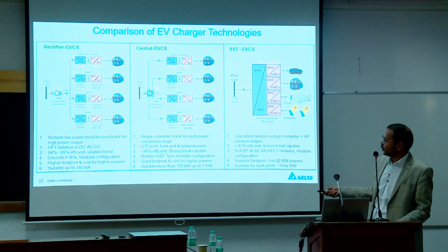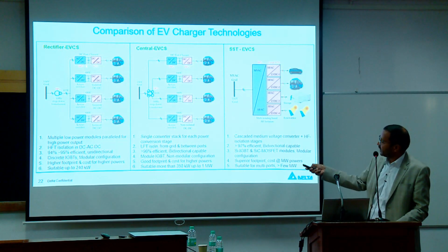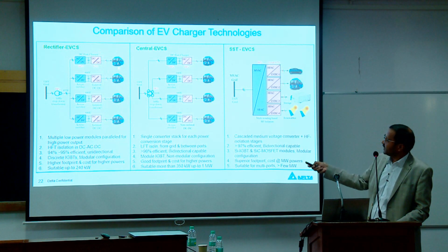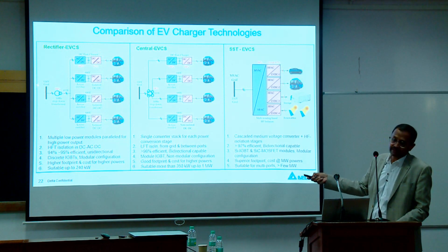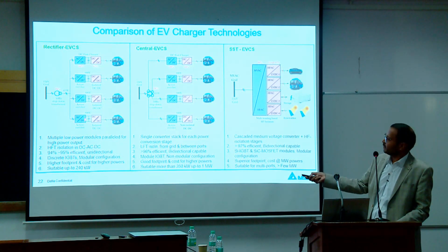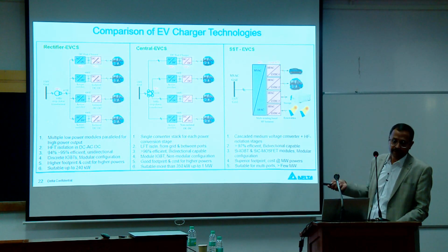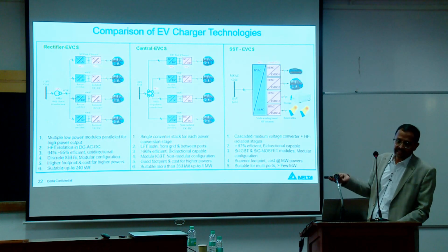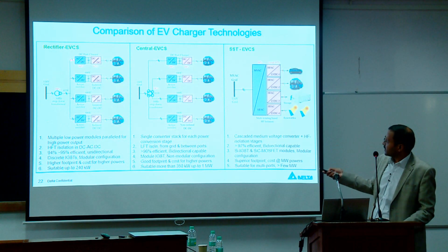But from the efficiency point of view, you cannot achieve anything more than 94-95%, because this transformer is mandatory. If you see let's say 4-bus charging, that means you need something like 500 kVA of connection, so the transformer is mandatory from the grid point of view. If power is smaller, then it makes sense.